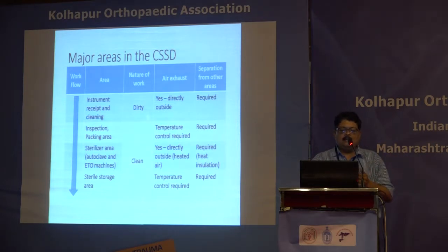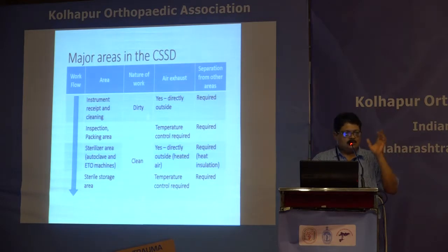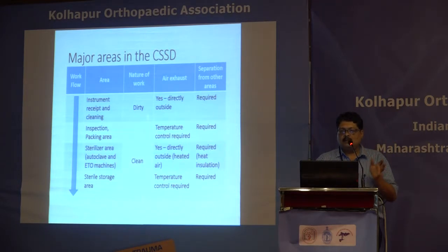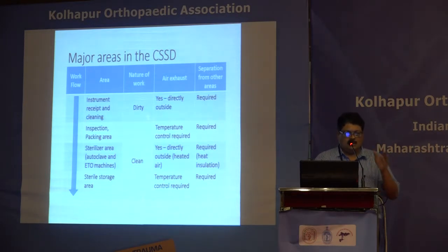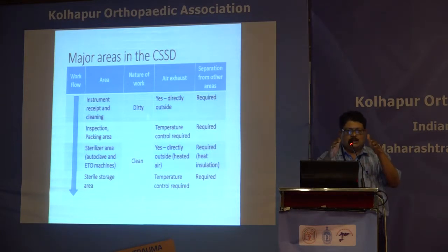The packing area requires temperature control because higher humidity and moderate-to-higher temperatures encourage bacterial growth. Western guidelines specify an AHU with HEPA filter air supply, six to twelve air changes per hour, controlled humidity, and completely separate staff. That is an ideal CSSD, but all this is not possible in our settings, so in our CSSDs some amount of risk of recontamination will always be there.